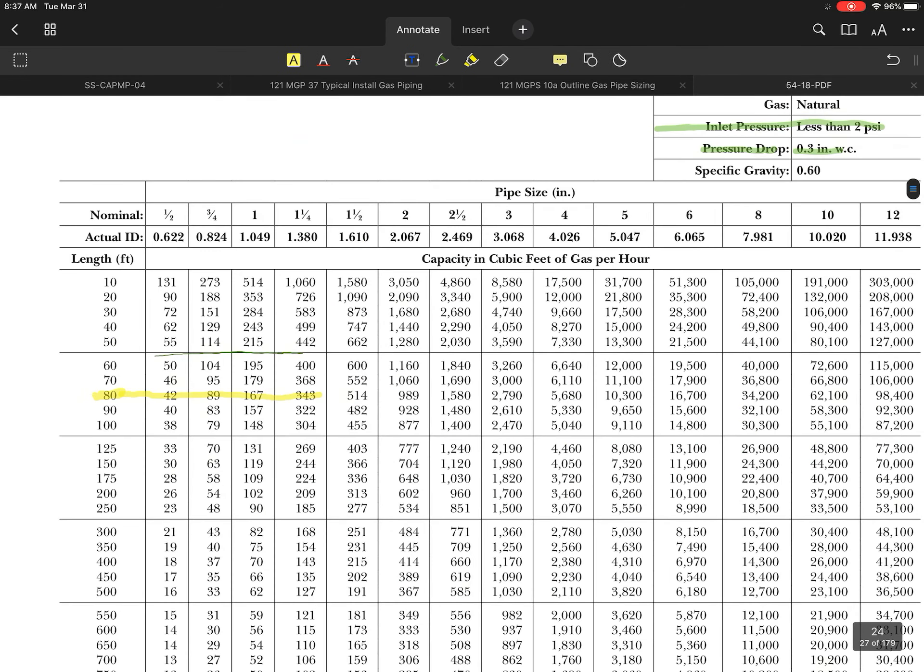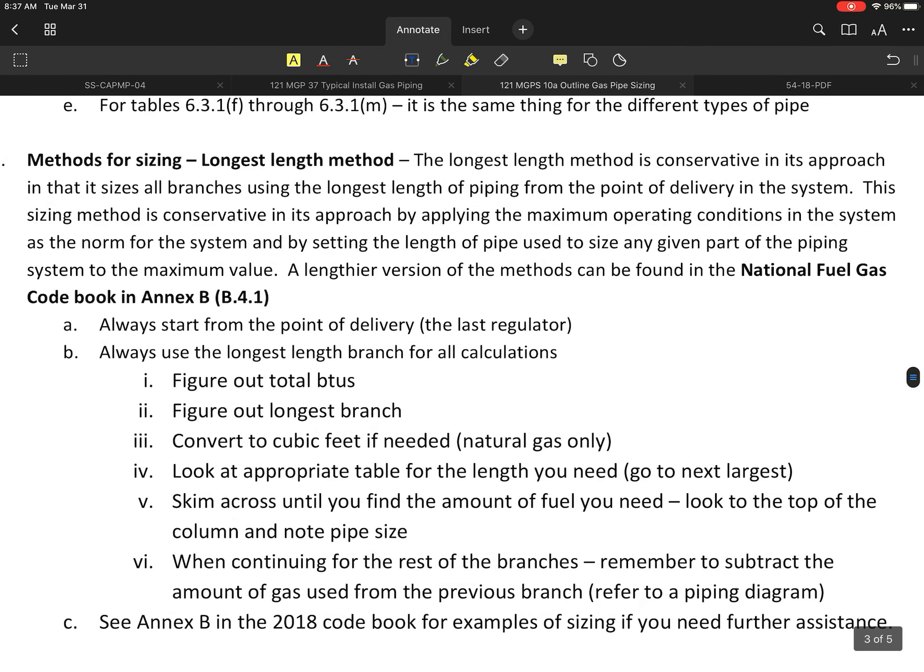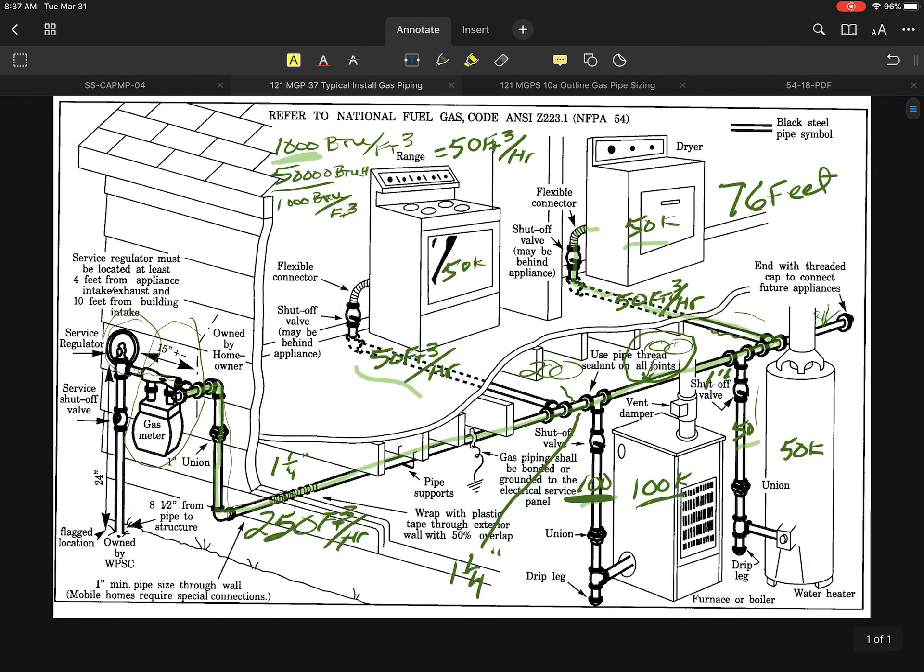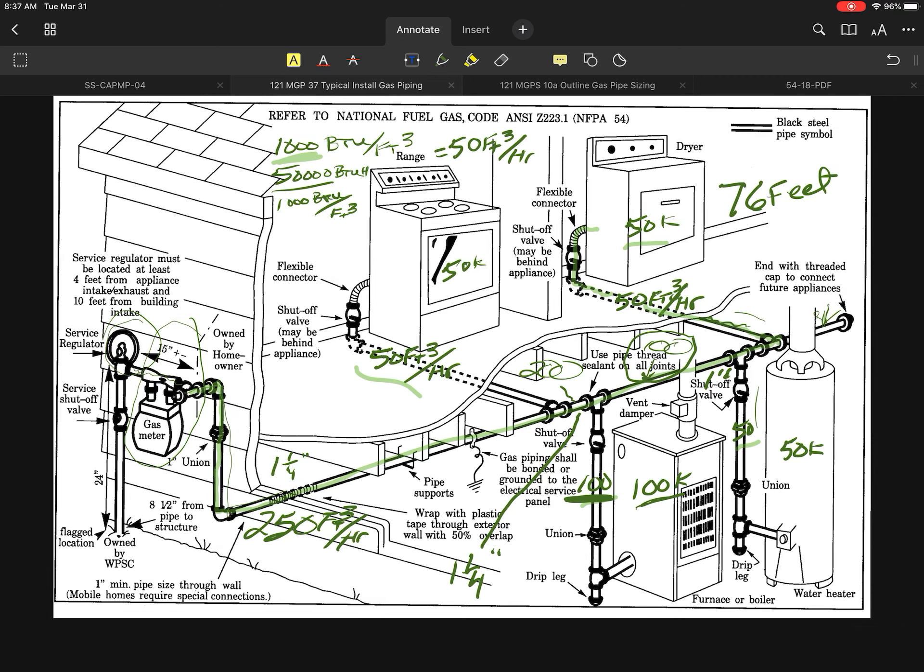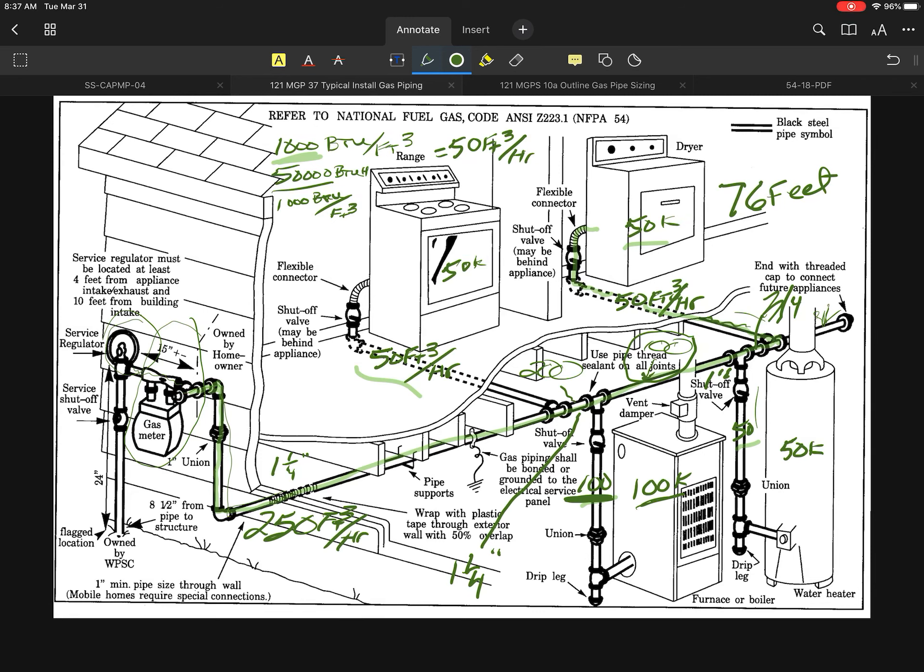The remaining two are going to be at 50. If I go back to my book, you can see that the next two lines are going to all be 3/4 of an inch because they can handle 89 cubic feet. Going back to the drawing, I can clearly see that every line here is going to be 3/4 of an inch, and that will also be true of the branches. Both of these two branches are going to be 3/4 of an inch.